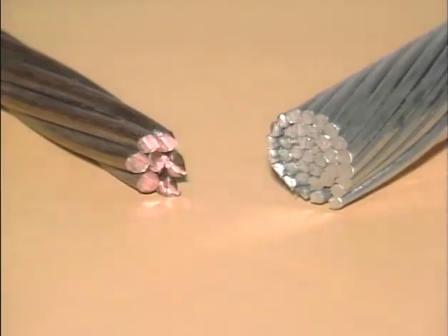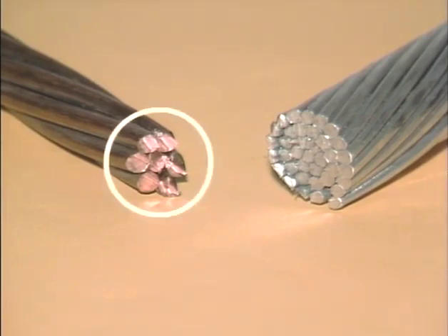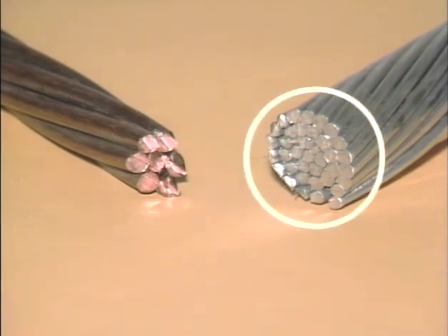In transmission and distribution, there are two materials commonly used in the construction of conductors. They are copper and aluminum. Copper is a commonly used line conductor because it conducts current very easily. Aluminum is widely used for transmission and distribution line conductors. However, it's not as conductive as copper. Even though aluminum is not as conductive as copper, it is lighter and lower in cost, which accounts for its wide use.